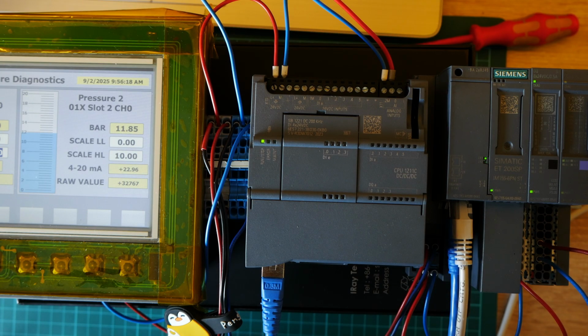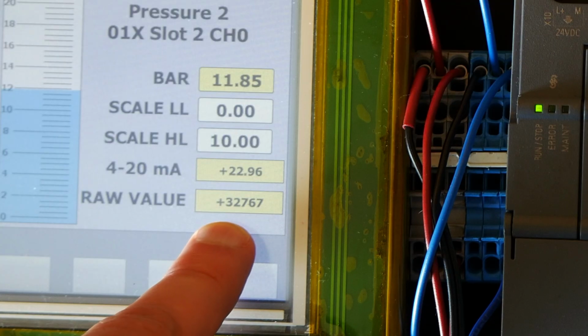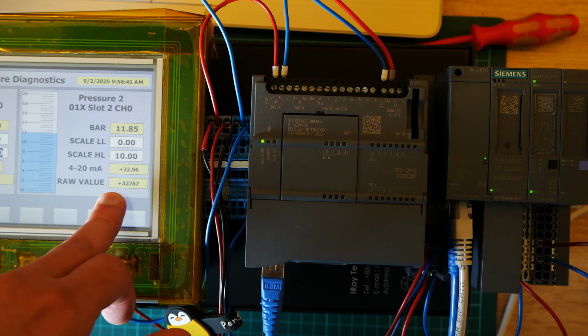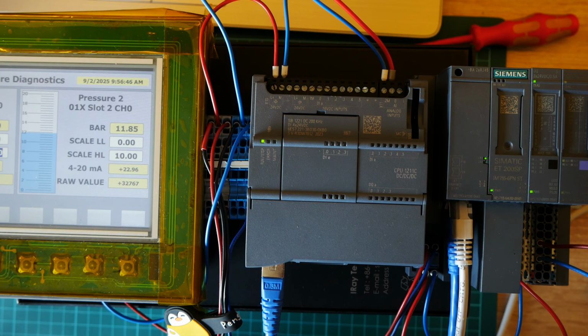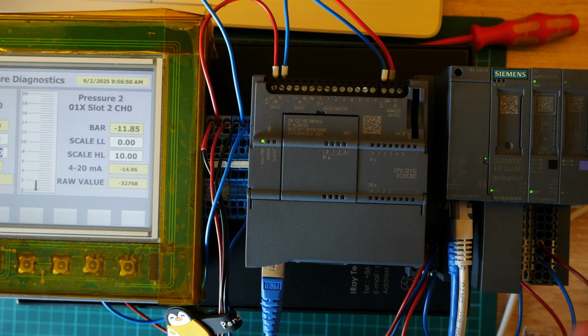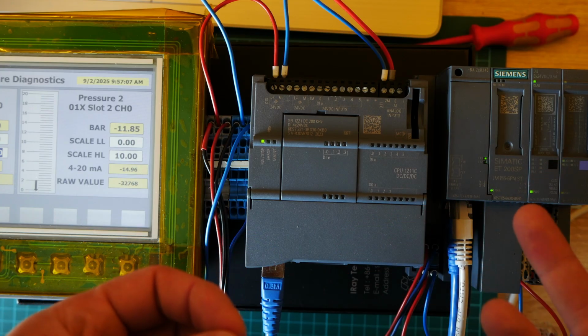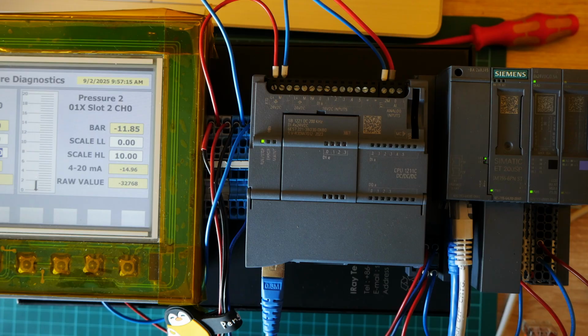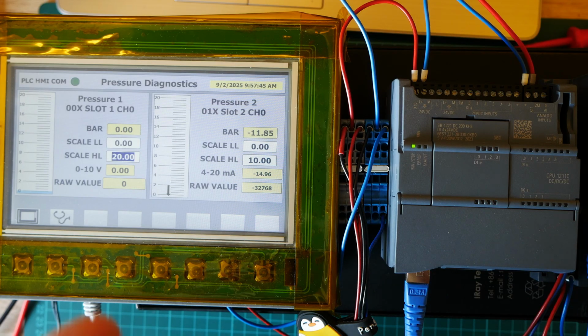If you have a shorted loop, let's say your transducer has liquid damage or something, you should have plus 32,767. So it goes above the maximum value. This means you have a shorted transducer, something with the wires or something with the transducer. Change the wires first, because wires are usually cheaper, and if the wires are shorted and you are too lazy to change them and you put in a new sensor, you can burn a brand new sensor. So wires are always cheaper. Change wires, then change the transducer.